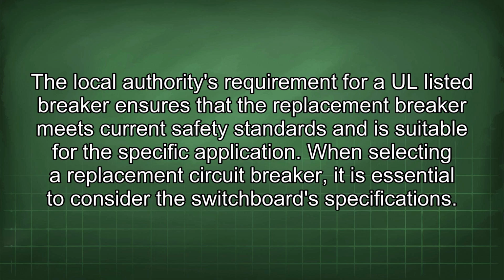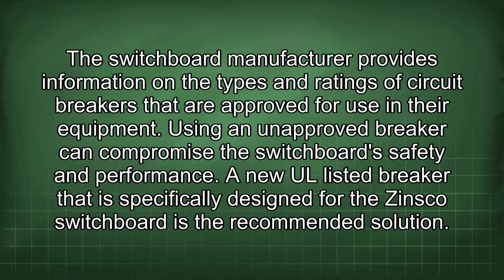When selecting a replacement circuit breaker, it is essential to consider the switchboard specifications. The switchboard manufacturer provides information on the types and ratings of circuit breakers that are approved for use in their equipment. Using an unapproved breaker can compromise the switchboard safety and performance.